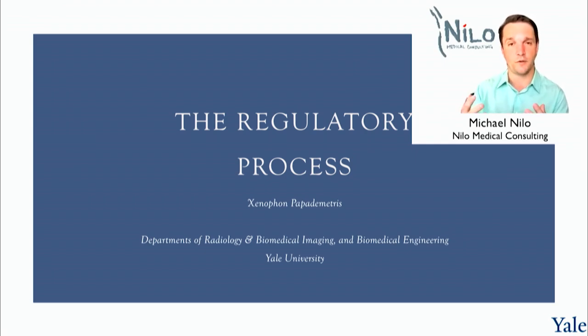With software, there's only those three main things that they can look at to show that your device works. And so you really should make sure that you're looking at the guidances and doing a full job of your software verification, validation, your human factors, usability, verification, validation, and your cybersecurity as well. So those would be the three things I would focus on if you're getting ready to go to the FDA, regardless of the class level.